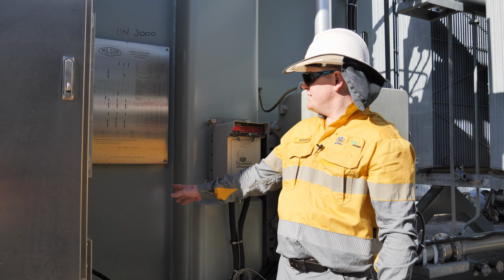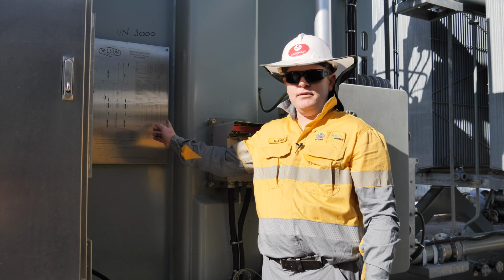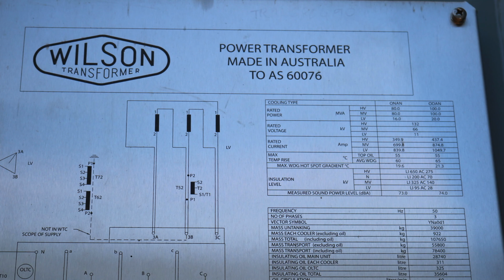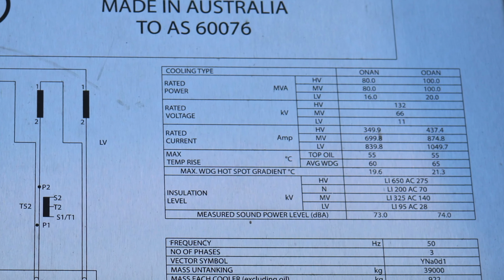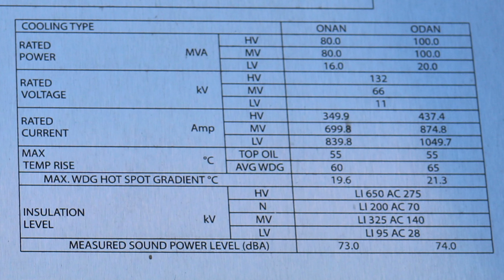Alright, so the specific details relating to this transformer can be found on the nameplate. On the nameplate here we can see that there are two ratings for the transformer, an ONAN, which stands for oil natural air natural, and we have an ODAN, which is oil directional air natural, which can also be referred to as OFAN, oil forced. The ONAN rating is 80 MVA, and the ODAN rating is 100 MVA, and that's the difference in rating that pumping the oil makes around the transformer. We can get an extra 20 MVA out of the unit.